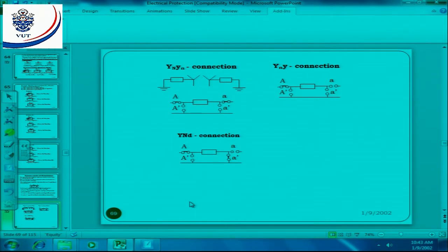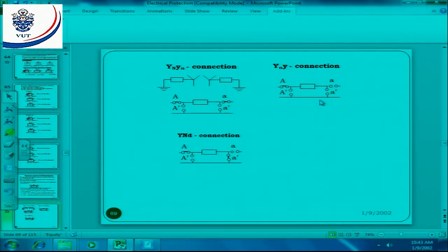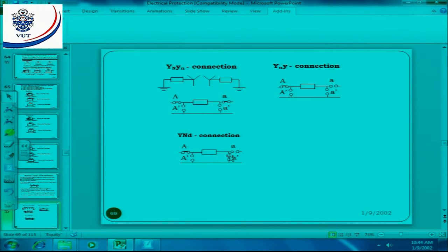If we look at a star-star with both sides connected, then A and A are connected. Where the high-voltage side neutral is connected and the star on the low-voltage side is open, no zero-sequence currents will flow after the transformer. Then if we look at a YND connection — the high-voltage side is star with earth so capital A is closed, and delta connection on the low-voltage side means lowercase a-prime is closed. So zero-sequence current will flow from the alternator up to the transformer, but after the transformer no zero-sequence current will flow.